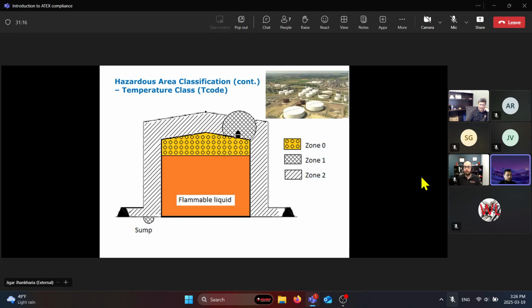So this is basically showing a different classification where there could be a zone 0, zone 1, and zone 2 environment all in one area. So if there is a zone 0 environment, again, like I mentioned, the method of protection there would be intrinsic safety. Anything installed in zone 0 would have an intrinsically safe output to a zone 1 or a zone 2. That's the only way that equipment would be certified to operate in such an environment, for example.